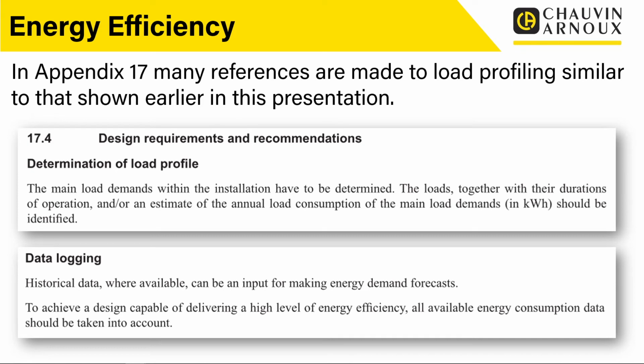Now, in the previous example, we looked at current demand, so we actually looked at the amps. However, they are mentioning kilowatt hours. That's generally what we would call energy. Kilowatts is normally power, and then you multiply that by time, and that's energy. So you have your energy meter within the electrical installation to measure your energy usage. So again, that's perfectly doable. That's just a different screen effectively when you're doing your surveys. So we can plot energy over time and look at what's going on within the installation, just like we did with a current survey. It just depends what you're trying to achieve at the time, but it's a similar process.